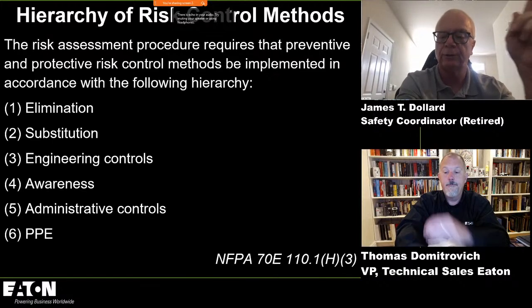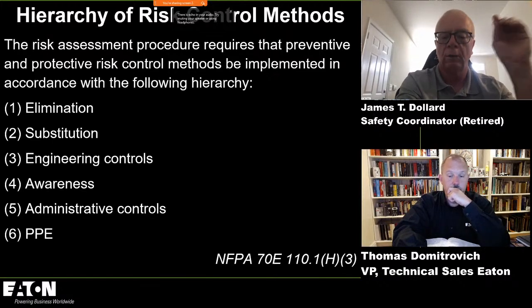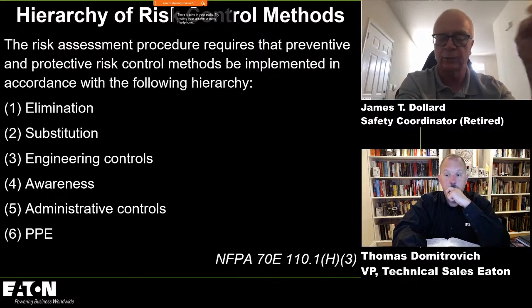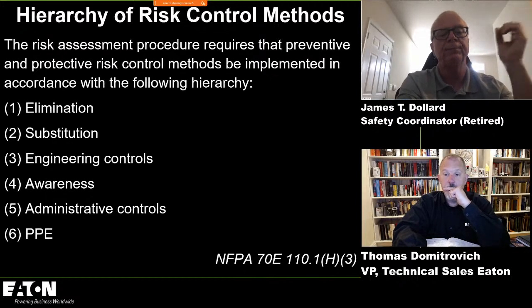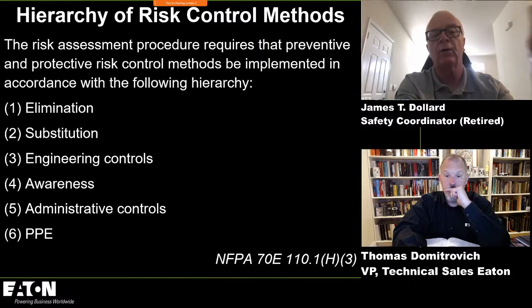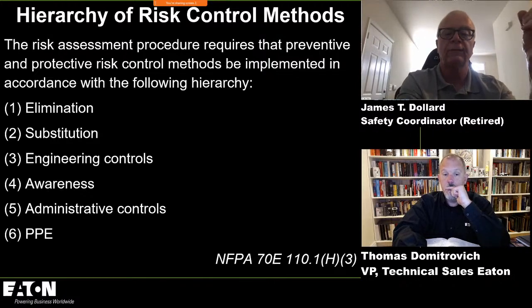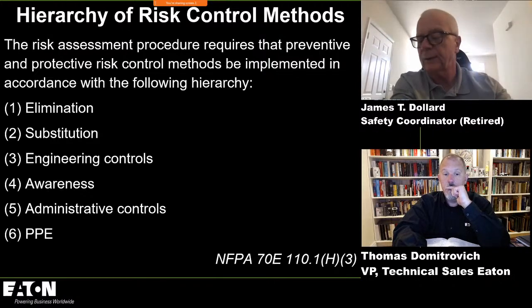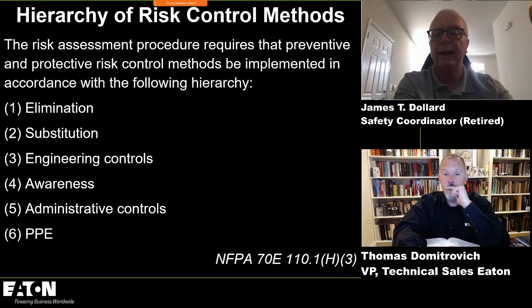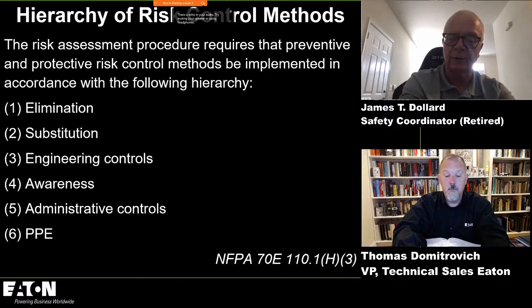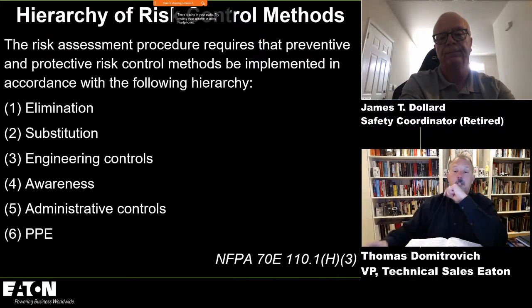You've got exposed energized conductors or circuit parts on the line side. So there's a shock hazard, there's a restricted approach boundary, there's a limited approach boundary. You've got an arc flash hazard, so there's an arc flash boundary. But let's take a look at what they did, Tom. When they opened that main, they de-energized all the bus and the load side of all those devices. Mm-hmm. So they significantly reduced the likelihood of an occurrence, but they didn't eliminate it. Interesting.